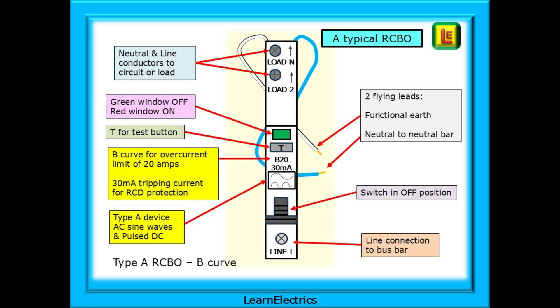This device has a residual tripping current of 30 milliamps. The B curve part is for overcurrents, and shown here is a B20 device. It will follow the time and current curves for a 20 amp B curve as shown in Appendix 3. Pause the video and take a moment to understand the sketch.